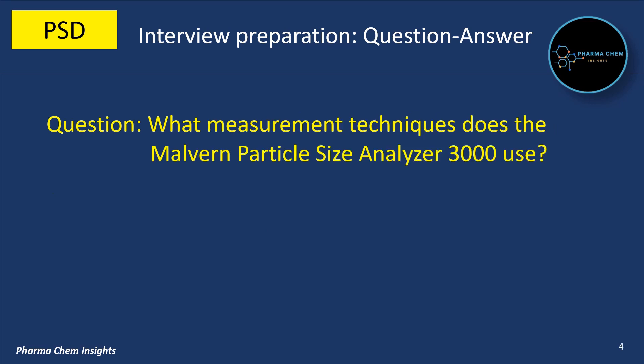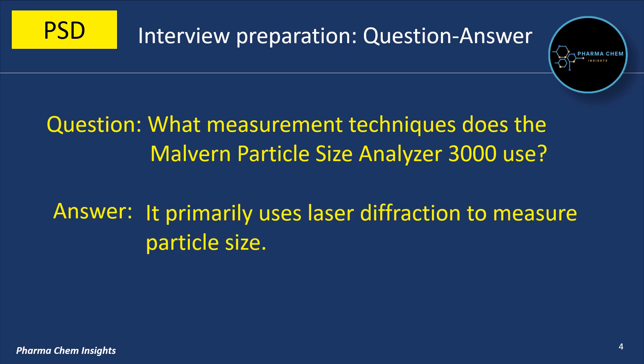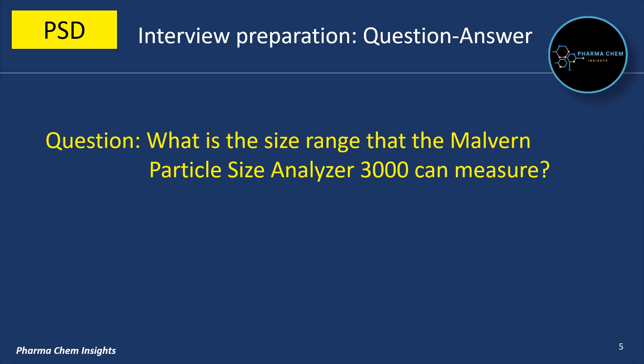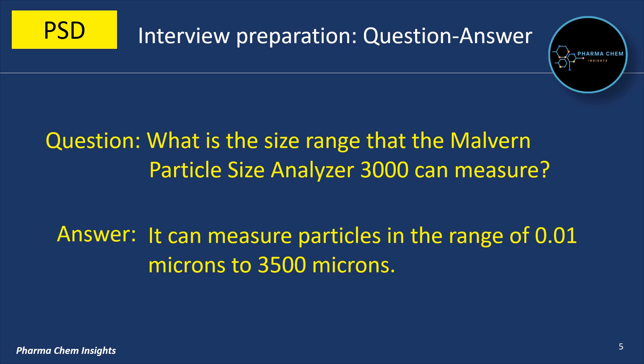Next question: what measurement techniques does the Malvern Particle Size Analyzer 3000 use? It primarily uses laser diffraction to measure particle size. It can measure particles in the range of 0.01 microns to 3500 microns.